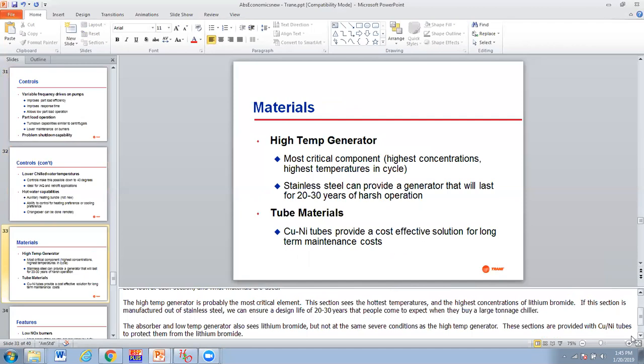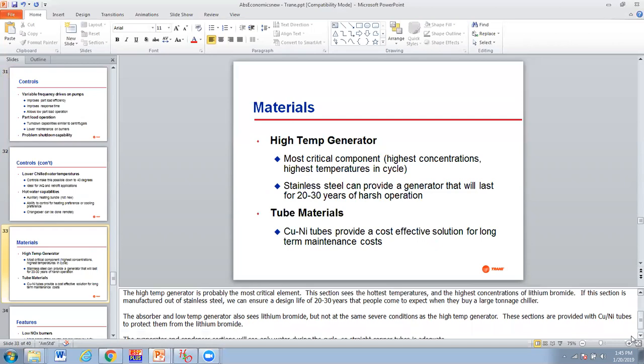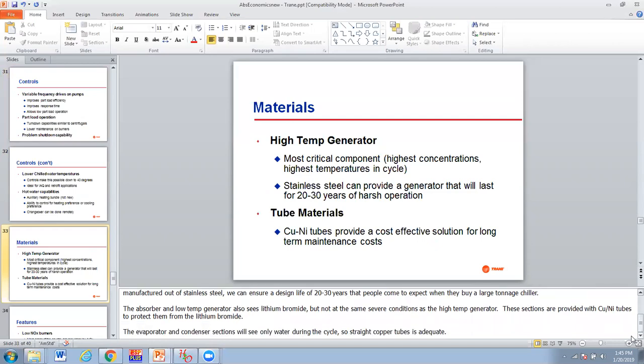The high temperature generator is probably the most critical element. It sees the hottest temperatures and also has high concentrations of lithium bromide. This section is manufactured out of stainless steel, which can ensure a 20 to 30 year design life. And so that's pretty good. A little on the expensive side, but still good.